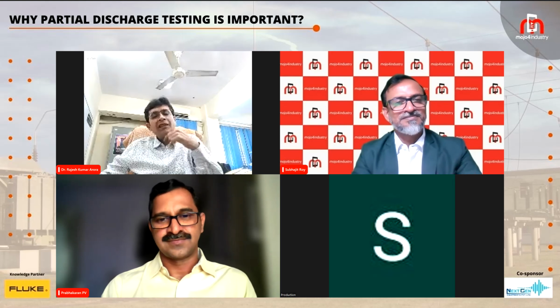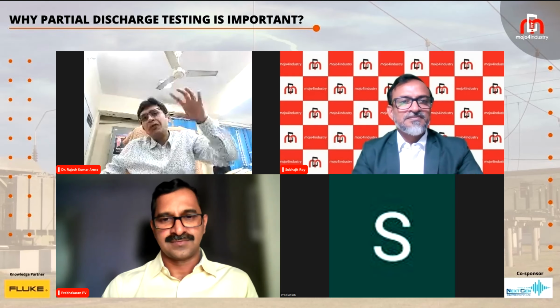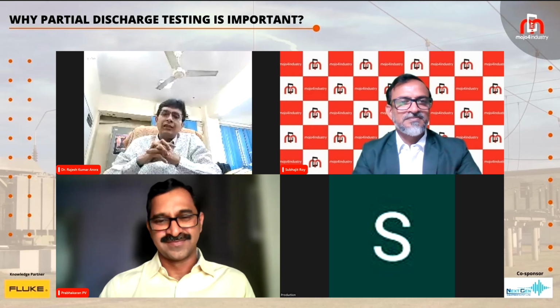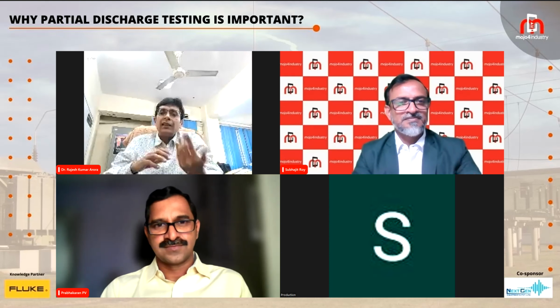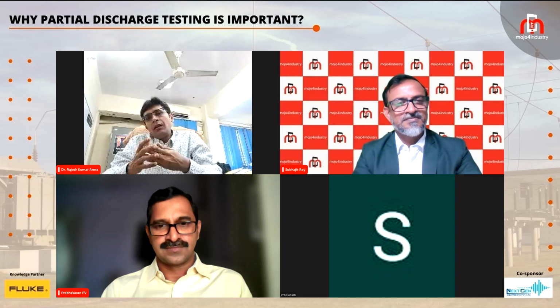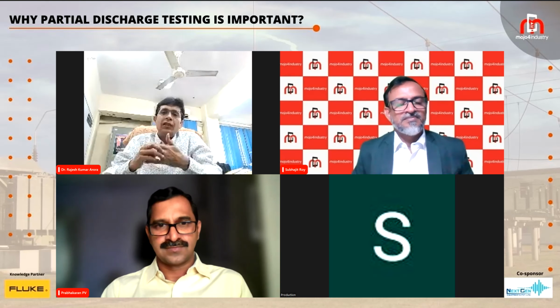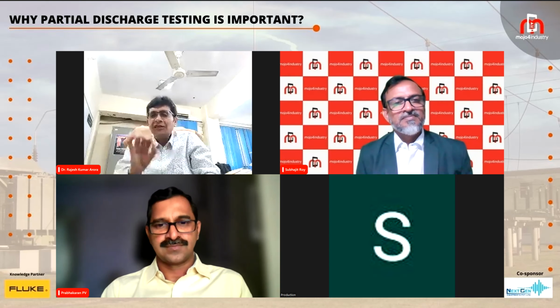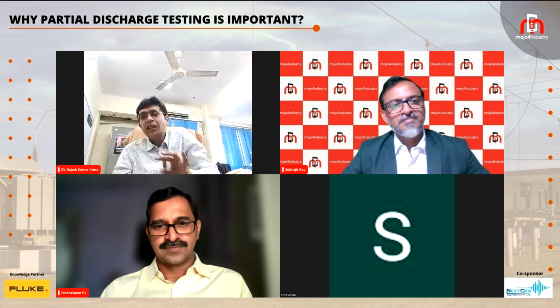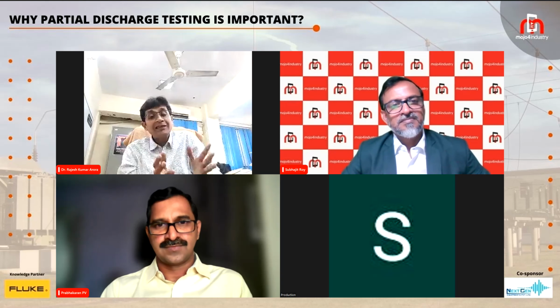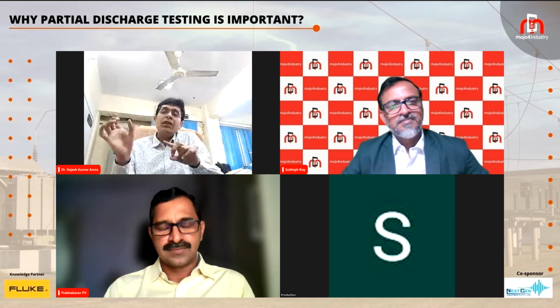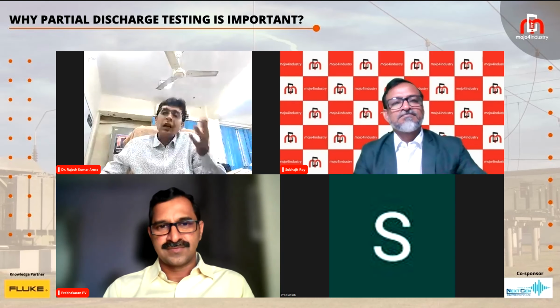For all these three types of insulation, we have to be careful how to detect a partial discharge. The phenomena for gas and liquid is quite different from solid insulators. There is some tracking effect, triggering and tracking. In gases, there is ionization, Townsend theory applies. You have to be very careful when doing partial discharge testing for particular equipment, and you should be able to pinpoint the exact location where the discharge is happening. As mentioned earlier, it starts with a very small impact, but finally it converts into breakdown. We have to avoid that.